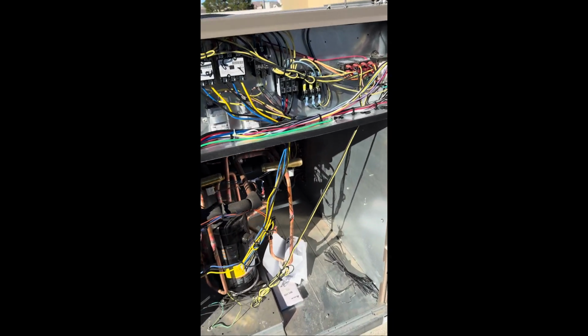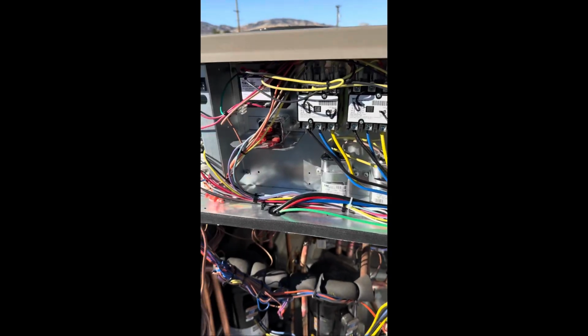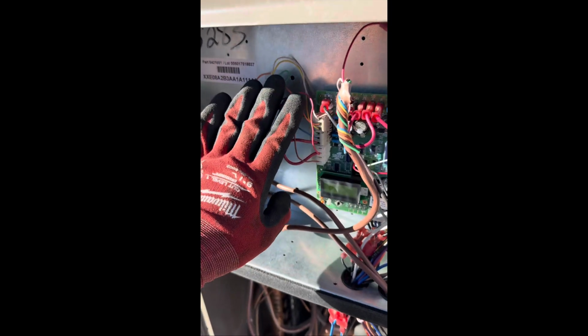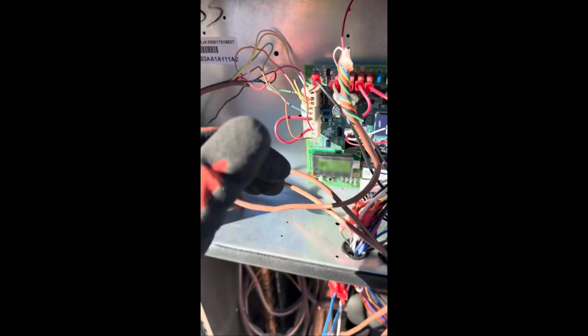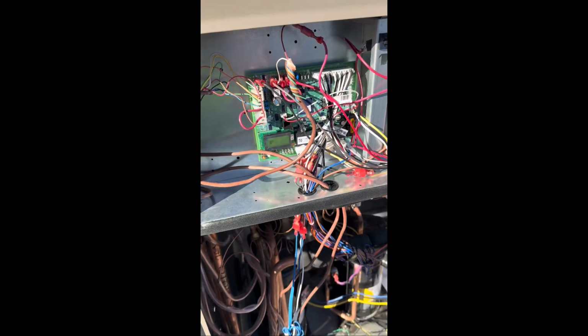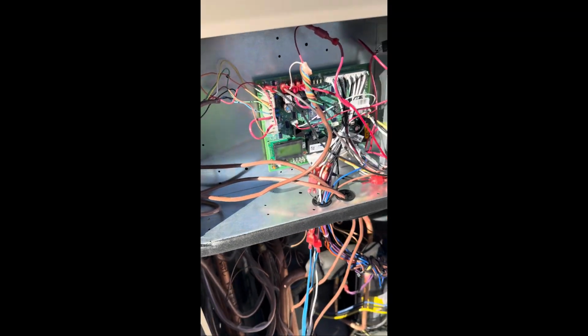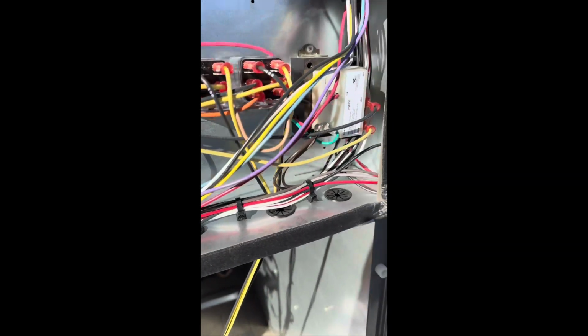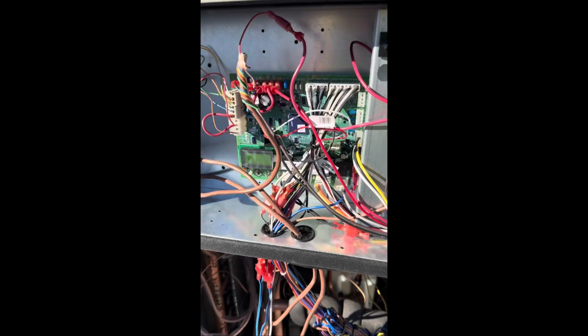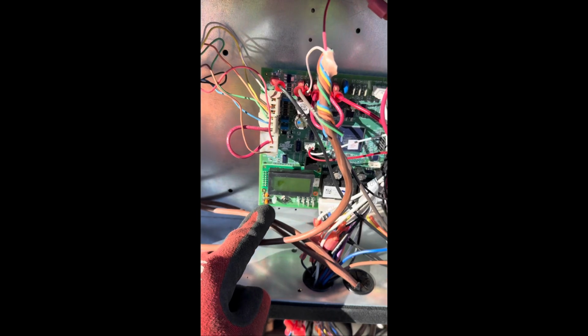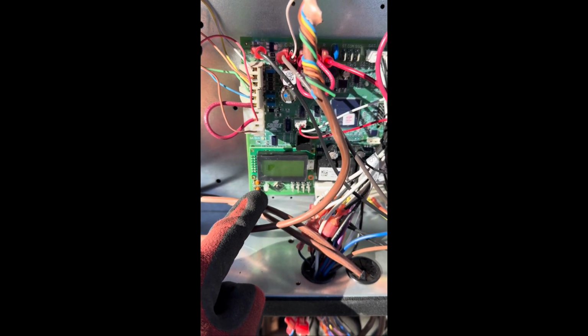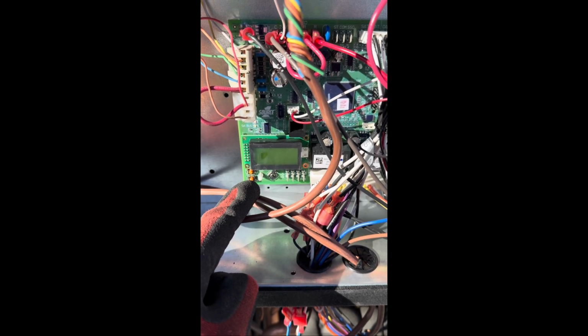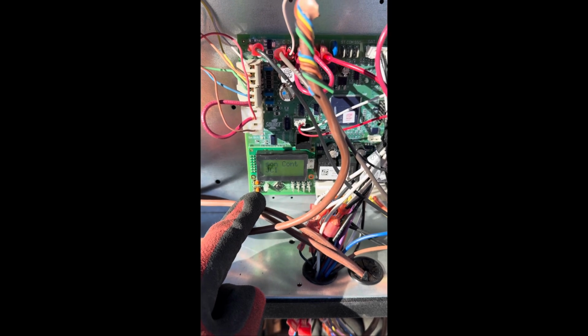All right folks, so now we're back again here. We have everything rewired, new wire ran. I'm going to tidy this up here in a little bit just to confirm we're not going to get anything. However, I've already done a continuity test. We should be good to go. So we're gonna power this bad boy up, and we got power, no breaker trip here. Very good. Should see the UCB power up here in just a second. There we go, all good to go.